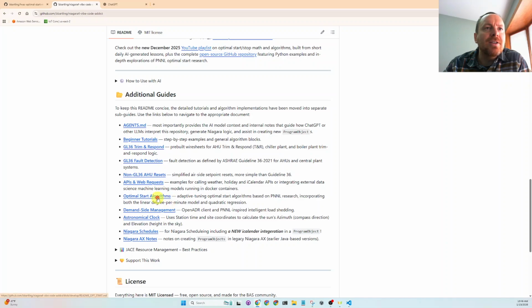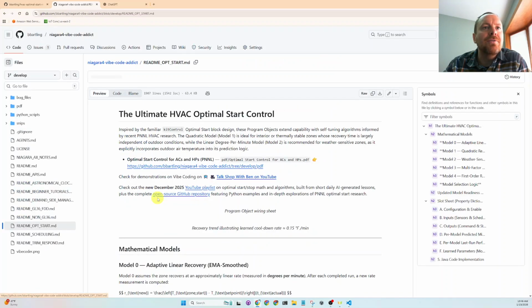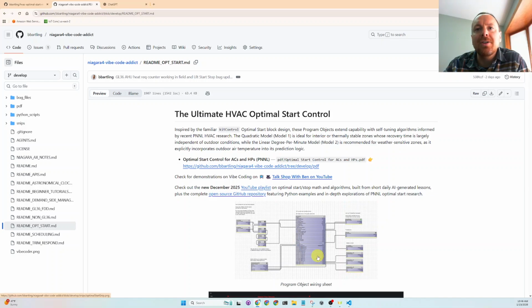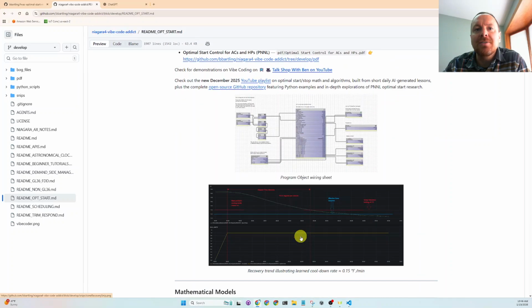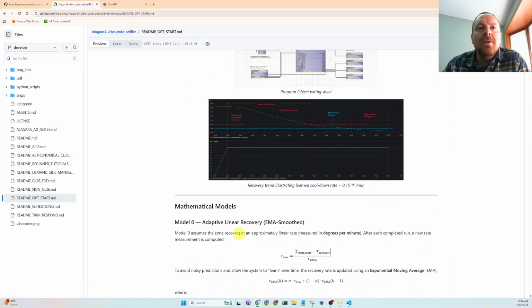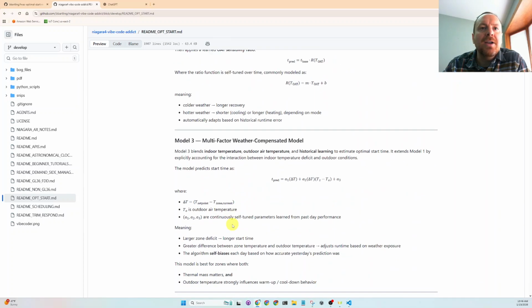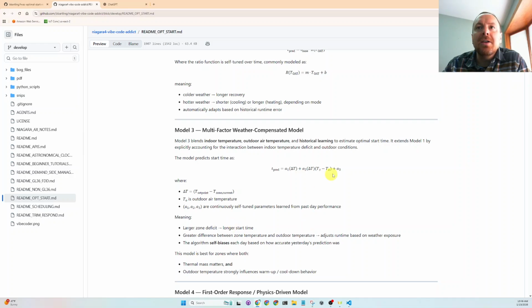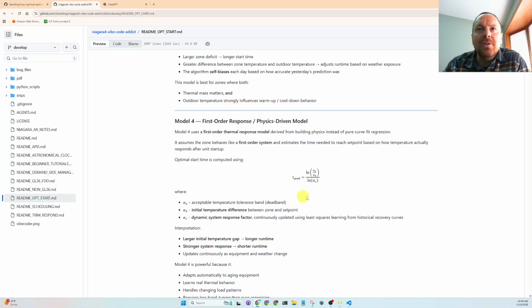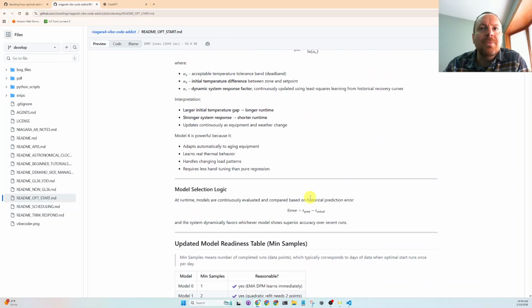I have this actually running in the field right now. This is the Niagara framework, which has been kind of nice for testing this stuff out. We have all four models defined by PNNL, except we're doing the multiple linear regression all manual, doing all the matrix multiplication ourselves, because in Java world there are no math libraries.